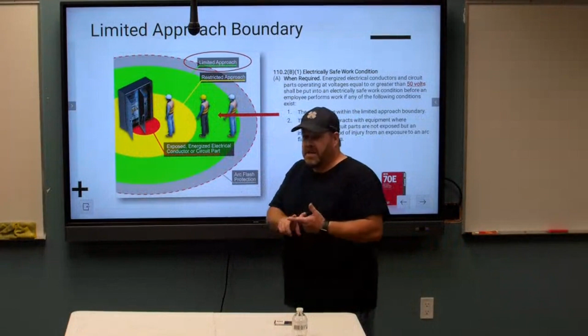Now the 70E does have exceptions, okay? If it's infeasible, meaning we can't turn it off and lock it out because we've got to test and troubleshoot. We can't measure voltage with the power off, right? We're electricians. Sometimes we have to test and troubleshoot. So that would be one exception. If we're going to perform ultrasounds, thermography, visual inspections, but we don't cross the restricted approach boundary, those would be some other exceptions. But short of those exceptions, we have to turn it off and lock it out if we're going to be exposed at 50 volts or higher. Now, I'll show you a table before we're done. It's called Table 130.4(E)(a) for AC systems or Table 130.4(E)(b) for DC systems.